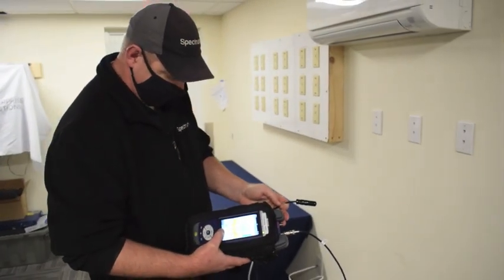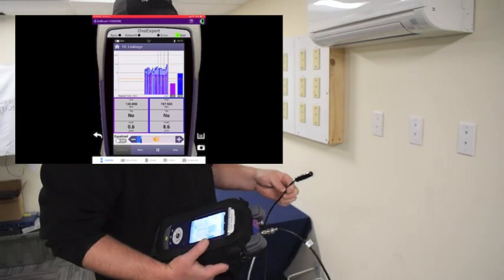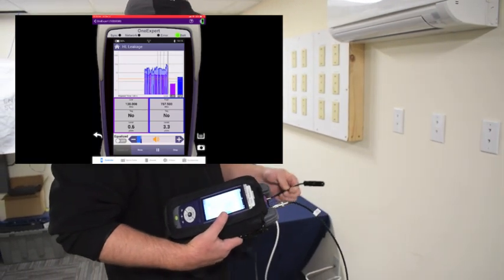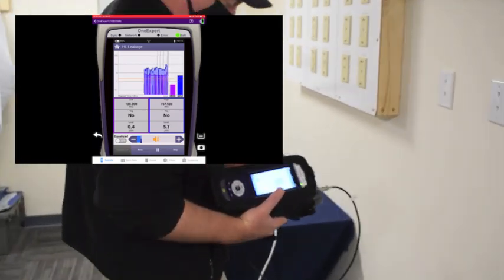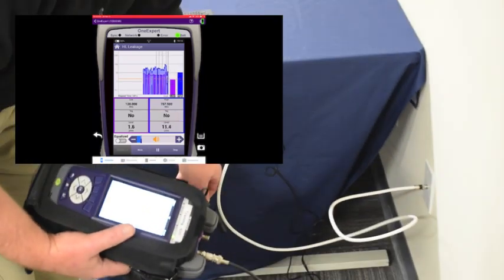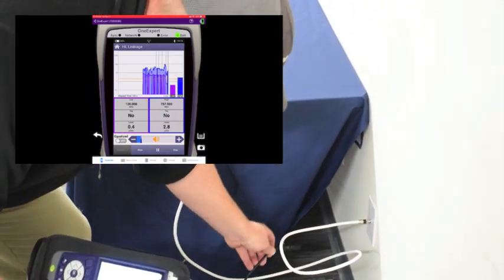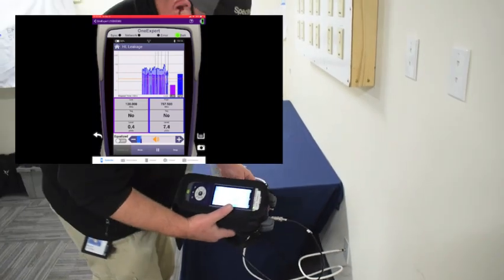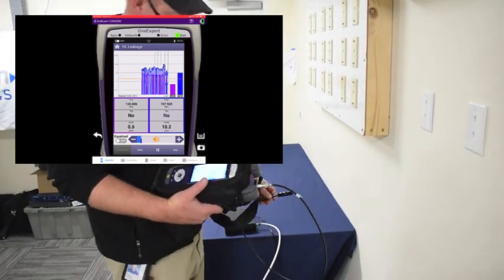Okay, to continue my test, turn the test back on, and then I'm going to take my near field probe and move it closer towards each object to determine where the leak is actually coming from. I'll start at the back of the cable box and determine if the leak is coming from here, which it is not. Even though the tagger hit, it's just picking up a leak in the area.